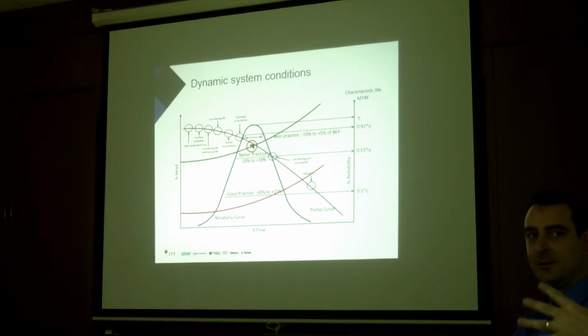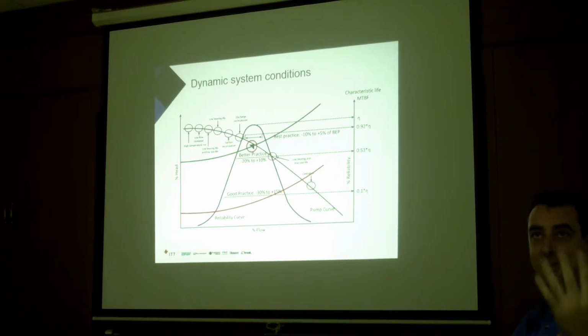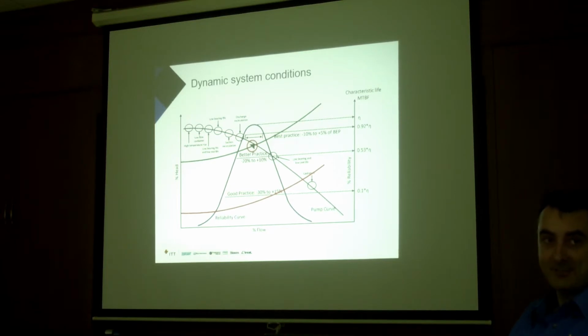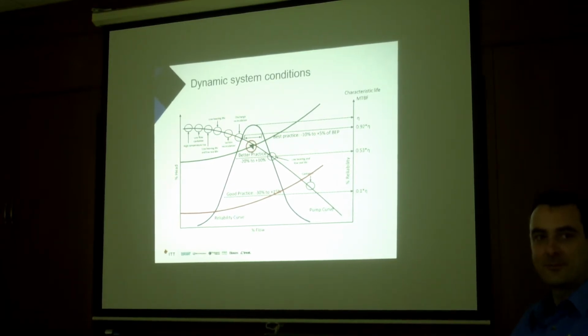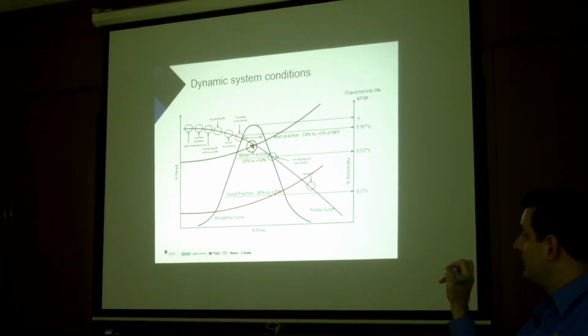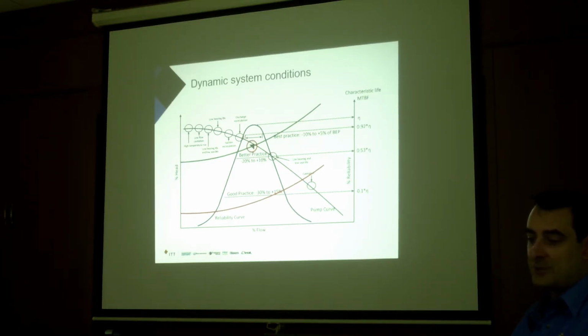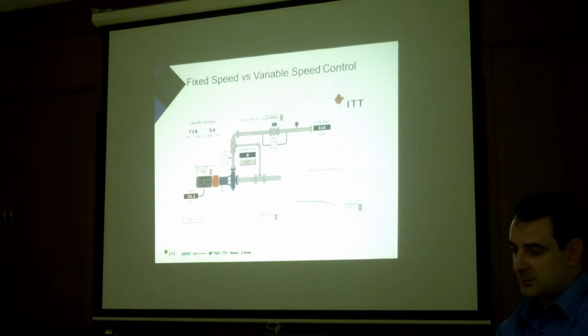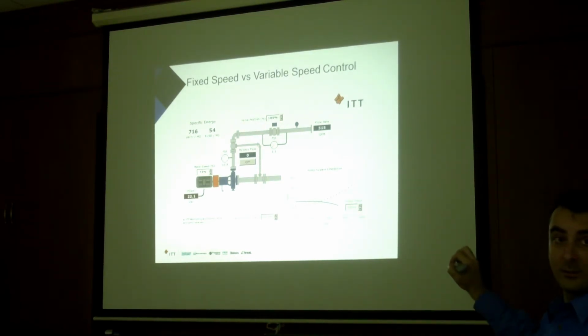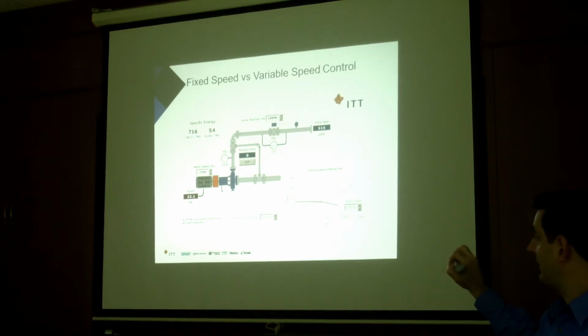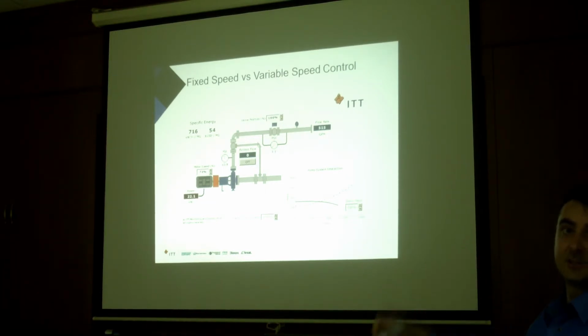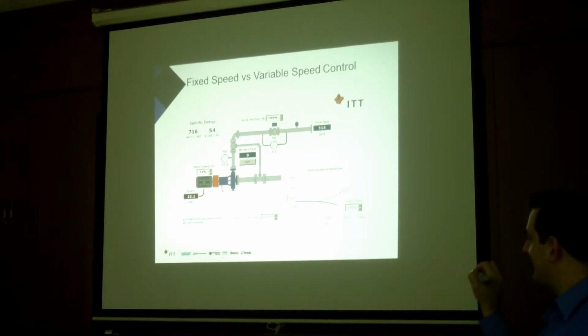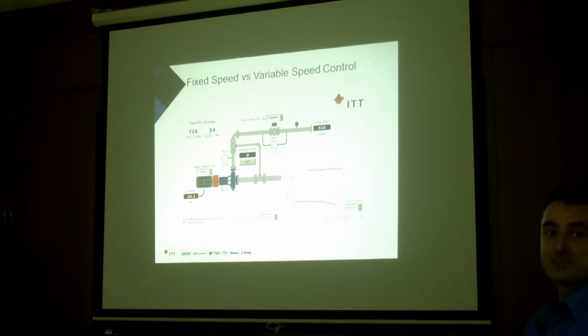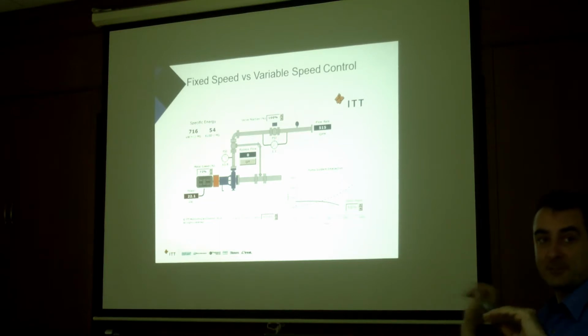So most times the one pump is sized for 4 arms, right? Yeah, so it's usually bigger than it needs to be. Because unless you get exactly 4 trucks with exactly an empty tank, you're never going to hit the maximum rated condition. But usually the problem that we have is that once you start lowering the speed, the pump might run off the end of the curve. Because, like I said here, the problem can be that when you have a high tank level, the speed to give you the pressure needs to be lower. So here your pump's designed for 4 arms, but here it can only do 3. So when that happens, we can do tricks. One trick is to look at the best efficiency point and deliberately increase the minimum speed, so that whilst you'll now have a higher pressure, at least the pump is not damaged.